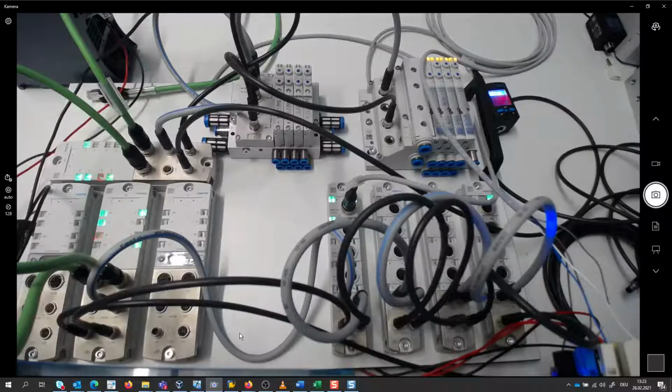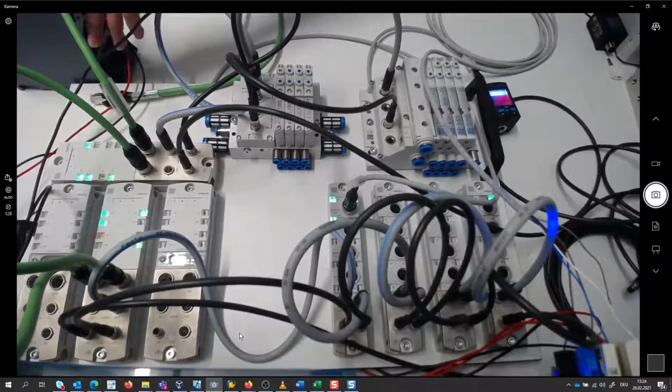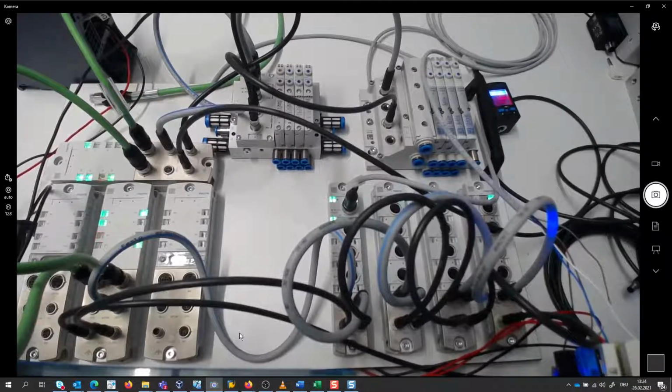What is very important, you see I have disconnected the cable. If I connect the cable again, the PLC builds up the Profinet relation to our devices again. And during startup, it will write the parameters which are inside the GSDML. That means with the API parameter block, you can change parameters during operation. But after a power off and on, this change will be overwritten by the PLC and the parameters set inside the module parameters of TIA portal. You see now, if I disconnect it again, we have the old behavior again. This is important to know, otherwise you may get problems with your application program, but if you take this into account, then everything is fine.